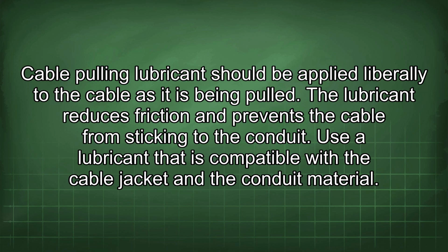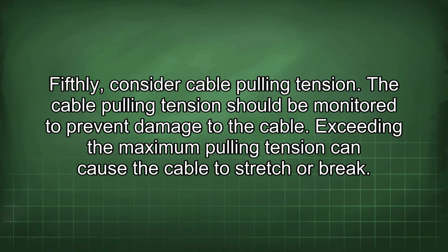Use a lubricant that is compatible with the cable jacket and the conduit material. Fifthly, consider cable pulling tension. The cable pulling tension should be monitored to prevent damage to the cable. Exceeding the maximum pulling tension can cause the cable to stretch or break.